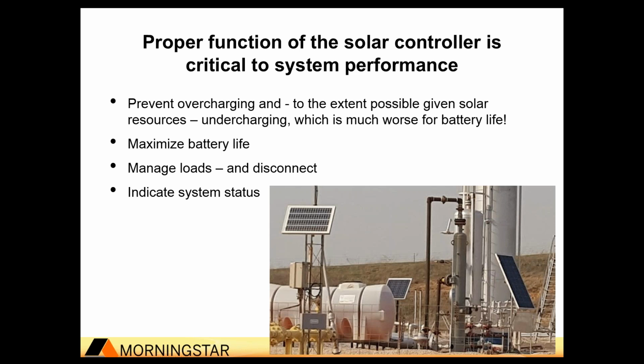In these kinds of cycling applications, like you see pictured in this particular site, the primary job of the regulator is, in a distributed solar environment, to prevent individual batteries or battery banks from being either overcharged, given too much current, which typically isn't a problem, but more importantly, the undercharging. That's really where systems go down or become at risk of going down, and it's also really bad for battery life.